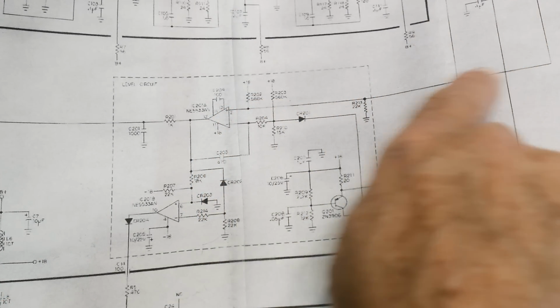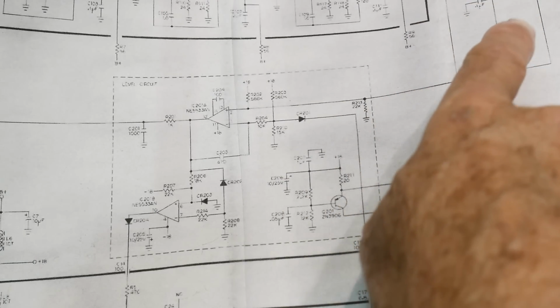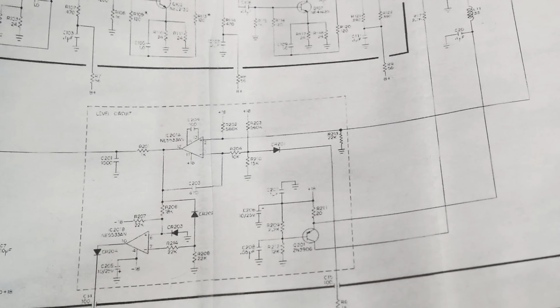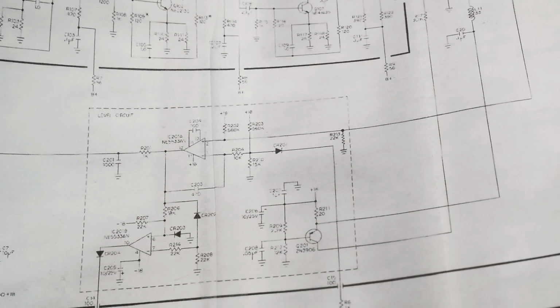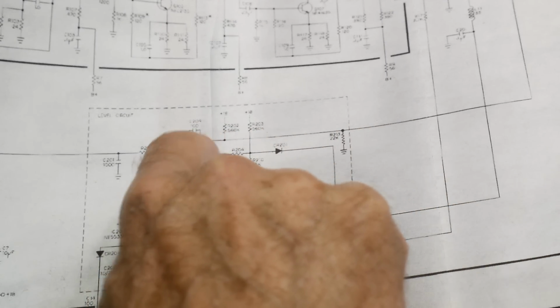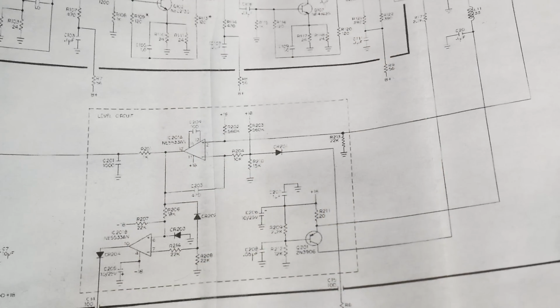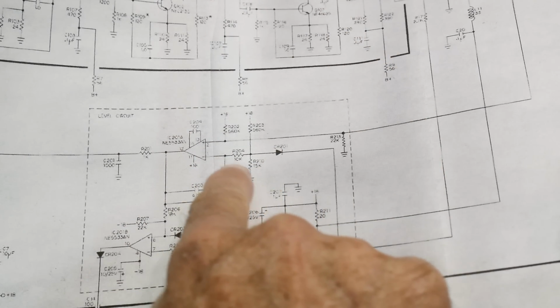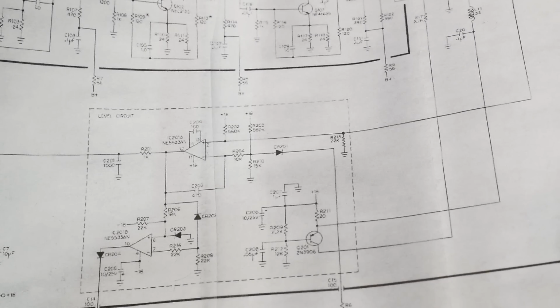All right, some progress here. So this voltage coming in from the detector diode is a negative voltage. It's around negative 3 volts or something around there, negative something or other. And so it's going and getting compared. So the other side should be about negative 3 volts as well. And if you take a look at this dividing string here, it goes to plus 18, not minus 18. So this is always positive.